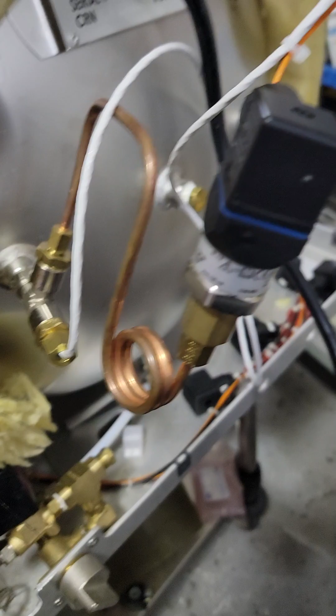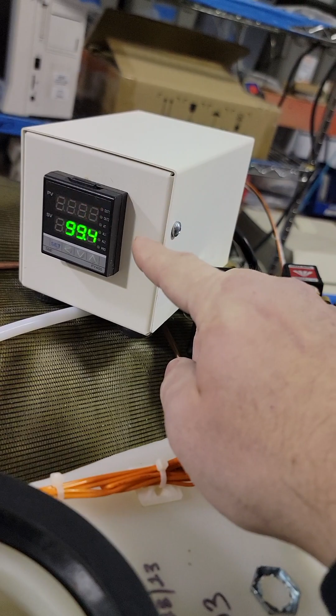Anyway, I'll put some funky voltages here. On the back end, you'll notice a few more valves, a needle valve, bellows. There's a test kit. There's much more features here than the other one, I guess, doesn't have. I don't know yet. This is the test block -- instead of teeing in a gauge, you've got this bad boy. It reads in Celsius, and I believe this is kPa absolute pressure. That's not in the charts, which is crazy. Here's a pressure sensor, kind of like the way Steris does it.